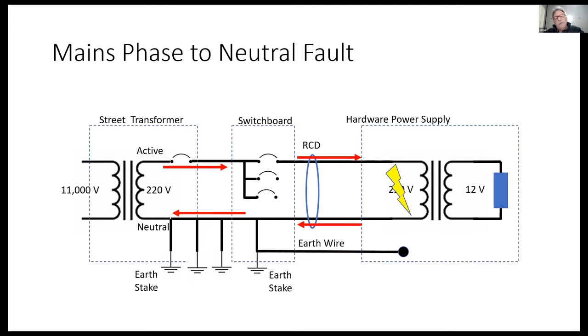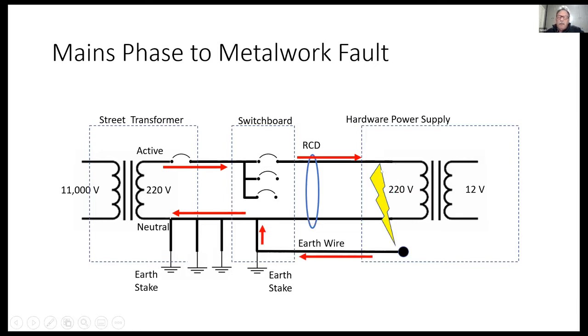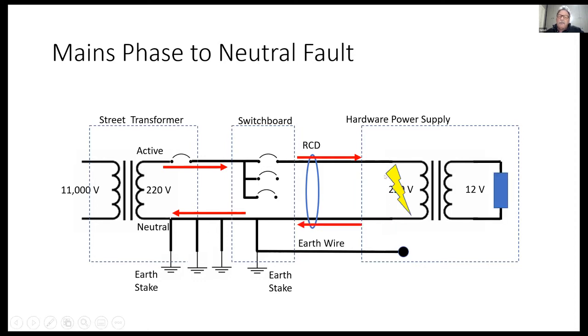Another thing we need to think about is the type of fault. So here, going back a page, I'm doing an active to earth fault, which is probably the most common type of fault you get. And here's an active to neutral fault, where the transformer primary's failed or something like that. But you'll see that in this condition, the current still flows down the active and back down the neutral, and nothing in the earth wire. So to the RCD, there's nothing wrong. There's a balance still there. The currents will be very high, but in terms of where the current is flowing, it's actually still flowing through the active and neutral. And what you get is not the RCD tripping, but the overload circuit breaker or fuse will trip. So you do these sorts of scenarios to work out where the current flows.